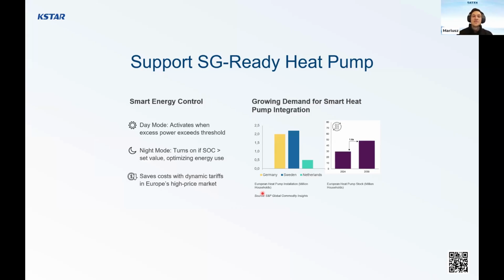We can also send a signal, for example, to some kind of external controller. And if the external controller sees a signal for increasing the electricity demand, it can, for example, turn on the air conditioner during the summer. So in the night mode, we will turn on if the SOC is higher than the set value, and there is no condition regarding the threshold.